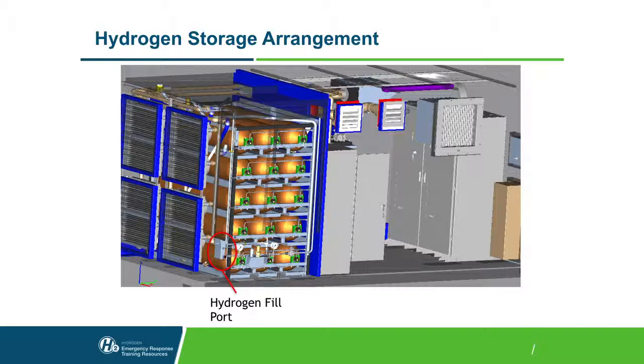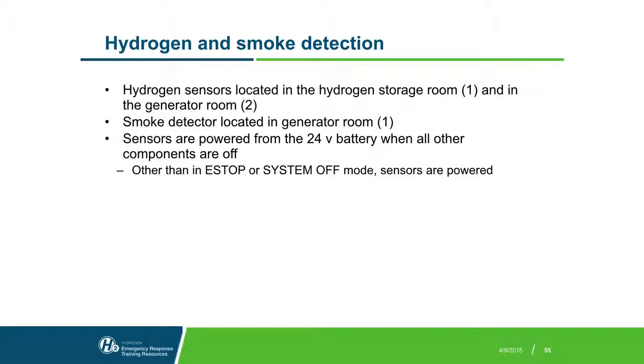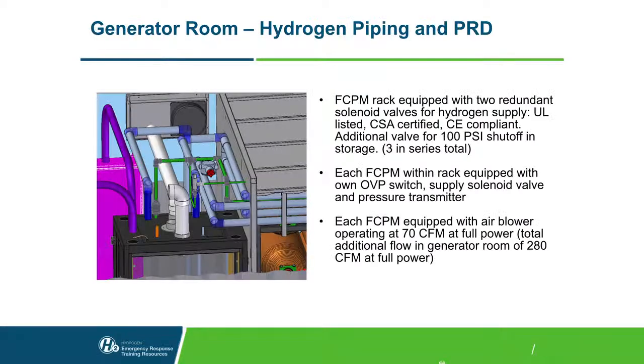When the unit's filled, again, this is the fill port here and some mechanical gauges. As we pointed out earlier, a hydrogen sensor in the storage room, 2 in the generator room, along with a smoke detector. There's a stage of the unit: there's on and operating and totally off, and then there's sort of this intermediate phase where they can do a leak check, and that is powering up the sensors with a 24-volt system, but it's sort of an intermediate stage of the unit. And the users don't want to leave that on because it would ultimately drain the 24-volt system if it isn't run and regenerated. Diagramming the hydrogen piping and pressure relief device here in the generator room, redundant safety for that.